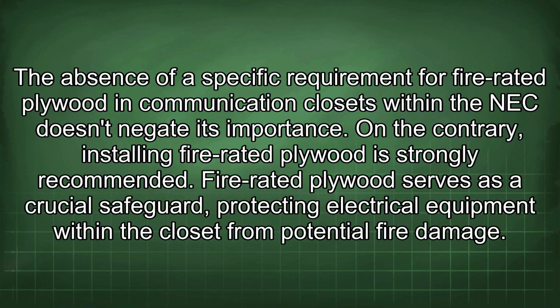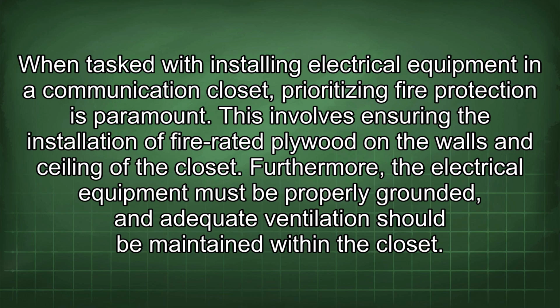The absence of a specific requirement for fire-rated plywood in communication closets within the NEC doesn't negate its importance. On the contrary, installing fire-rated plywood is strongly recommended. Fire-rated plywood serves as a crucial safeguard, protecting electrical equipment within the closet from potential fire damage. When tasked with installing electrical equipment in a communication closet, prioritizing fire protection is paramount. This involves ensuring the installation of fire-rated plywood on the walls and ceiling of the closet.